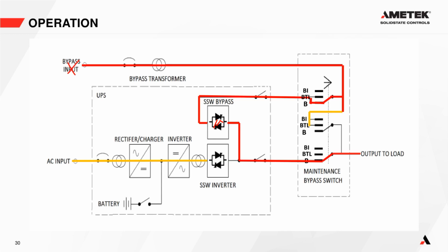So yes, as I said, we are discussing internally whether we should allow the customer to say, okay, you can have mode A of operation, which is what I just explained, or you can have mode B, where whenever the static bypass is on, if the bypass fails, then the inverter will take back over again. And then it will be the customer's choice which mode of operation they would prefer for their plant, because they may turn around and say, you know what, all I care about is this load. I never, ever want to lose power to this load. So I would prefer, even if somebody was going through a lockout tagout procedure, I would always prefer my load to be supplied. And that way you would choose option B, where it does transfer back to inverter to load if bypass was lost. So once again, very, very good question.